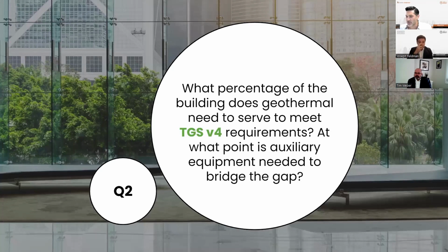The geothermal system serves 100% of the HVAC heating and cooling loads. It can do some domestic hot water, passively or actively, but by and large, domestic hot water production in a big mixed-use residential building is done differently or separately outside of the geo system.